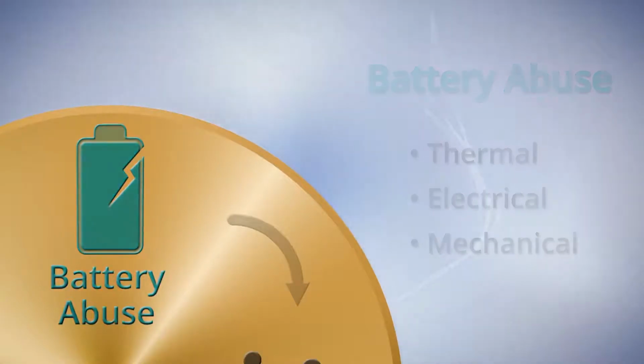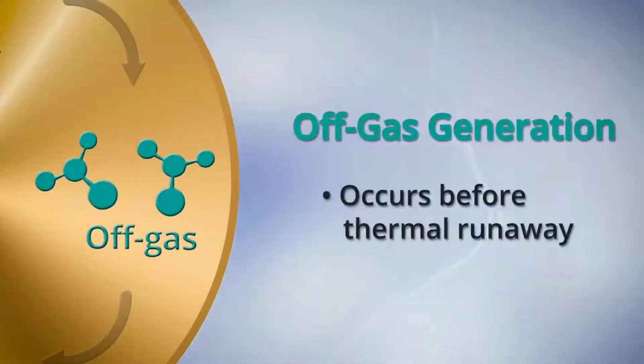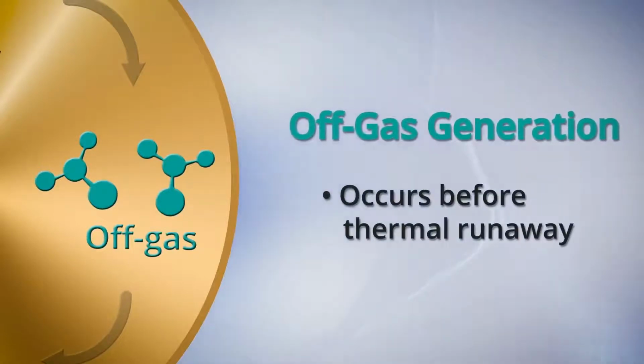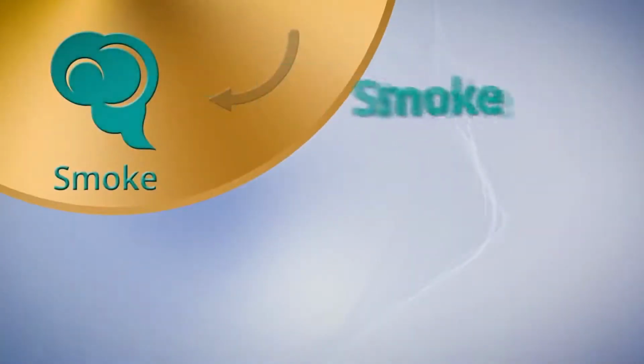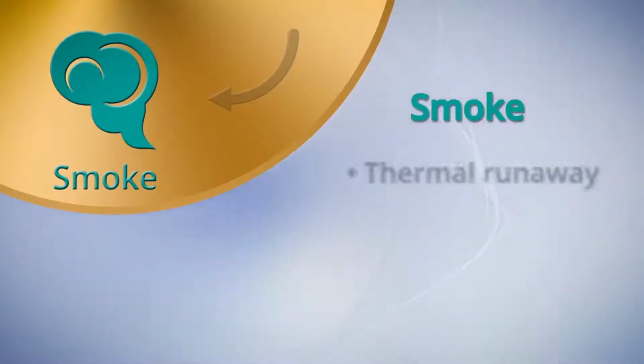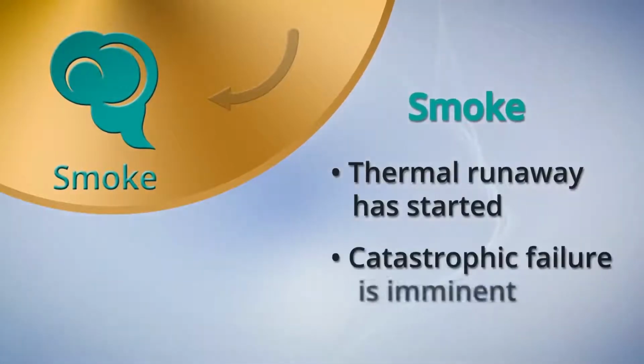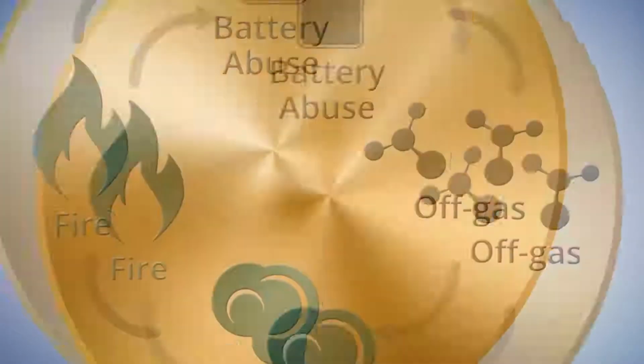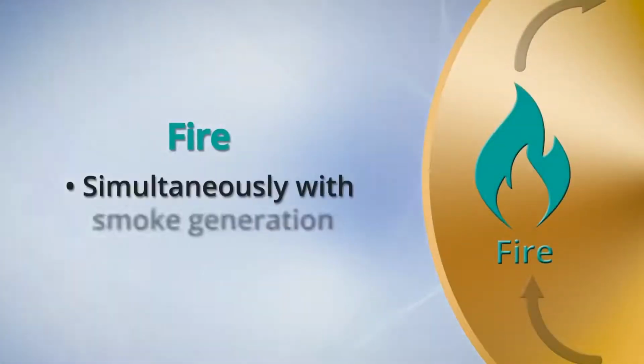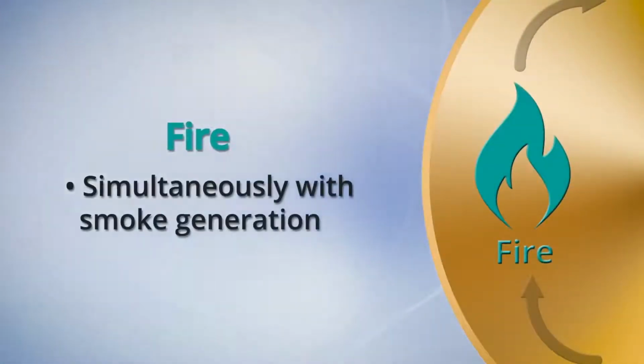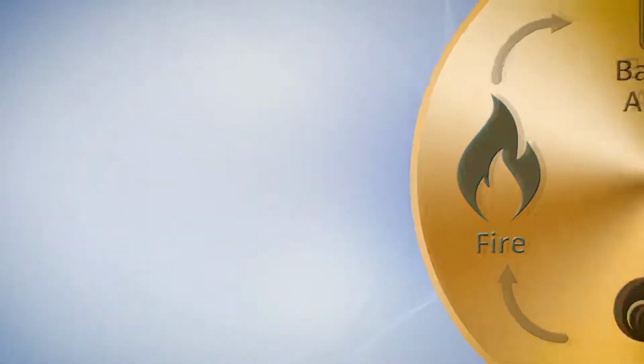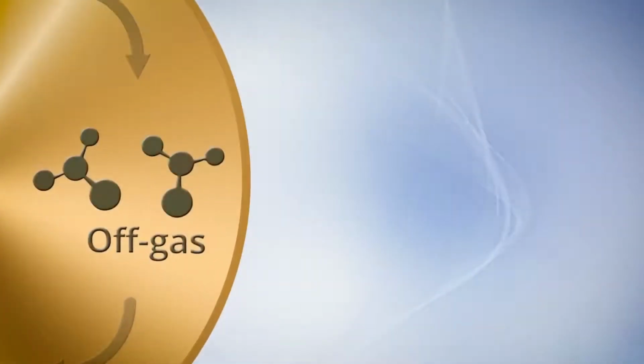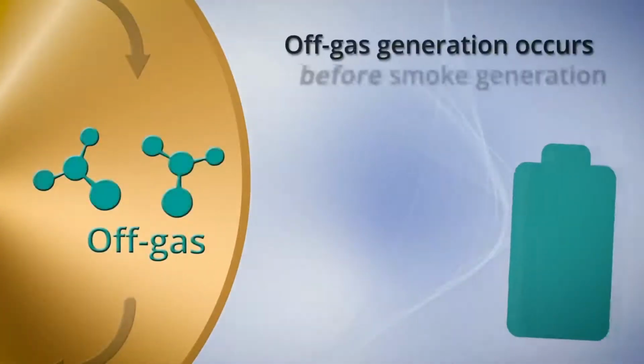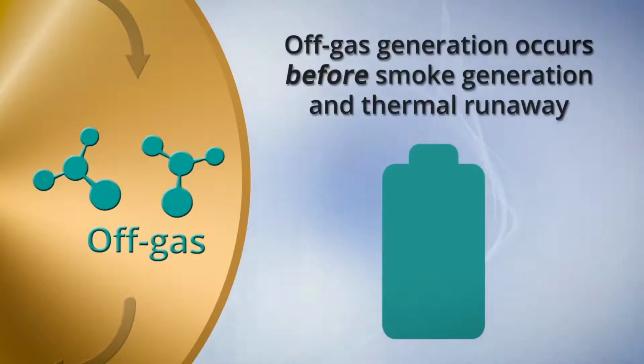The next stage is off-gas generation, which occurs significantly before thermal runaway. Then, smoke generation occurs, which means thermal runaway has started and catastrophic failure is imminent. Fire generation often takes place simultaneously with smoke generation, where propagation of the failure becomes significantly more likely. So let's look more closely at off-gas generation. It can occur anywhere from 2 to 30 minutes before smoke generation and thermal runaway.